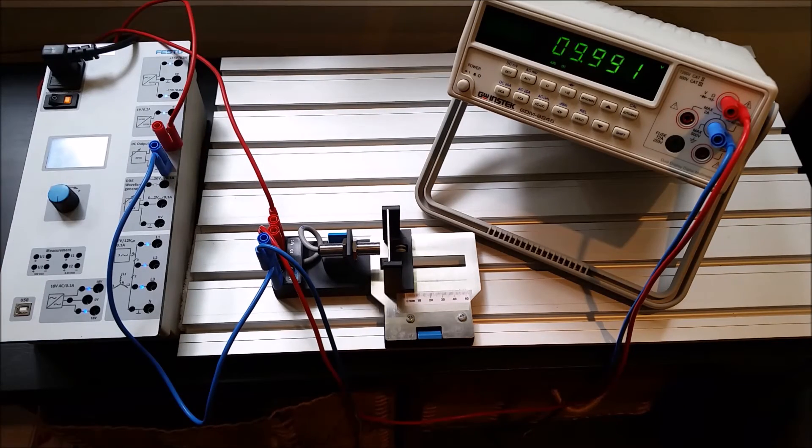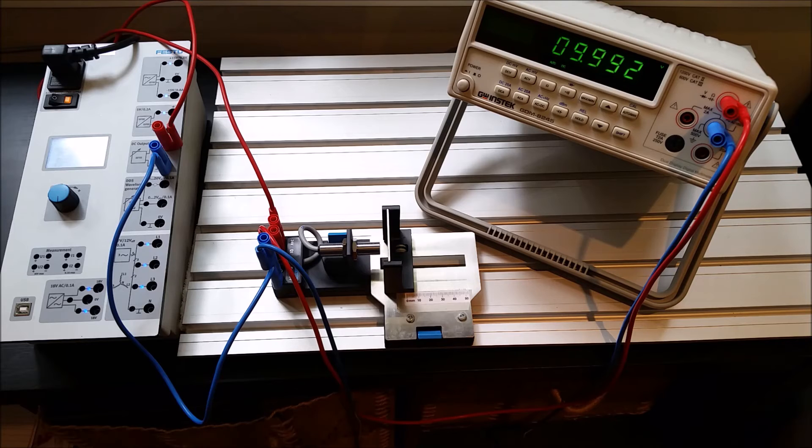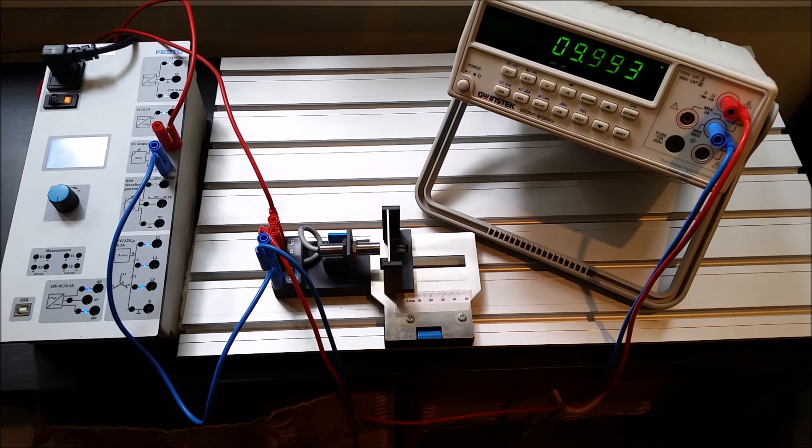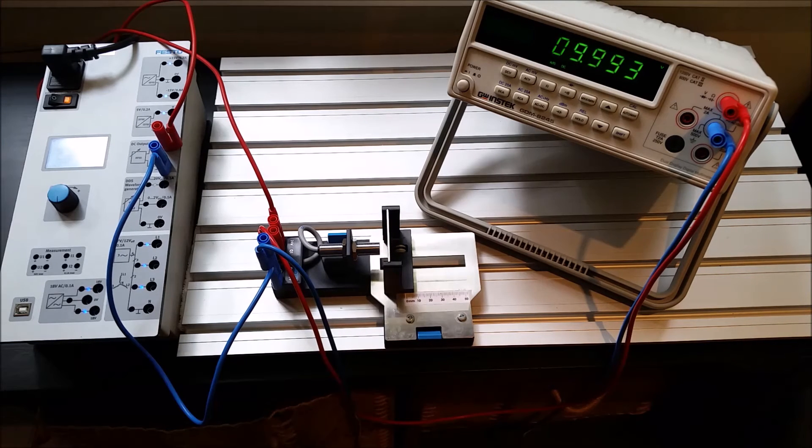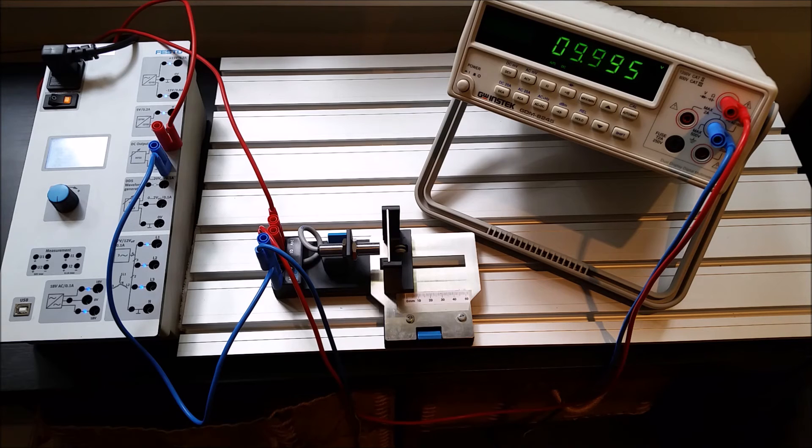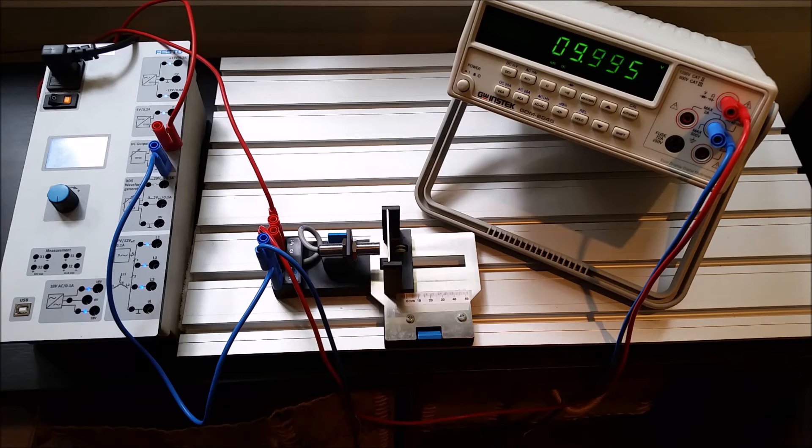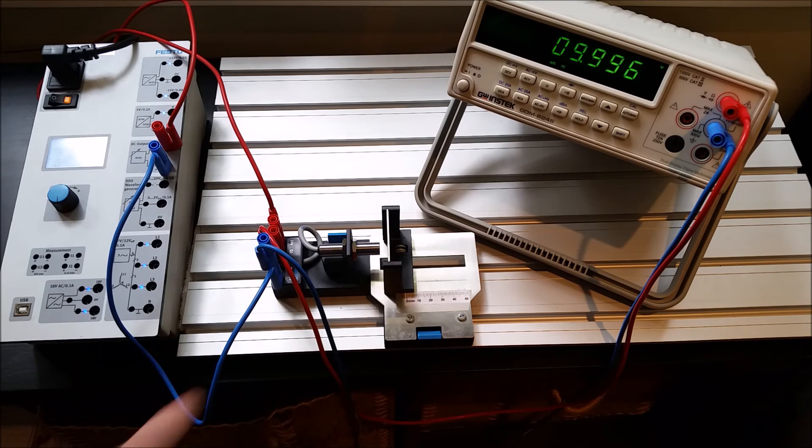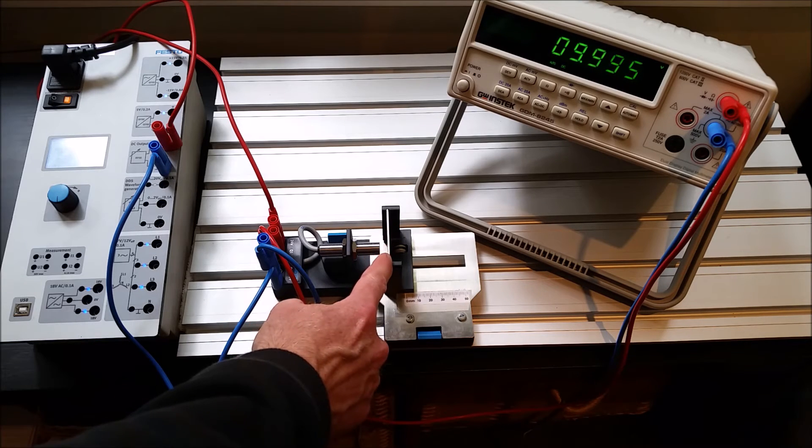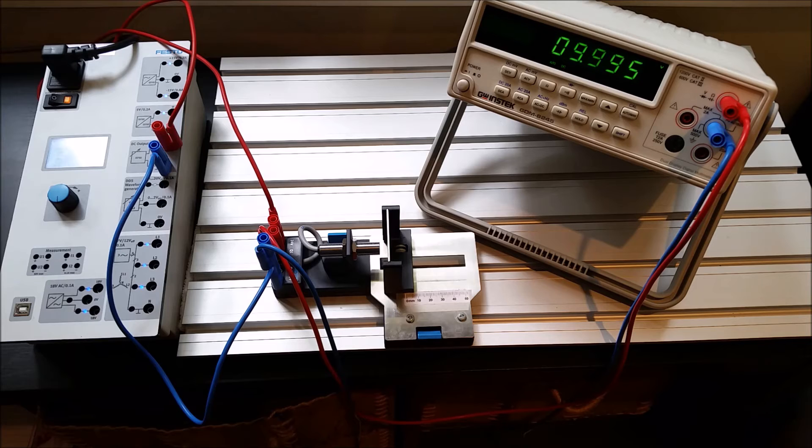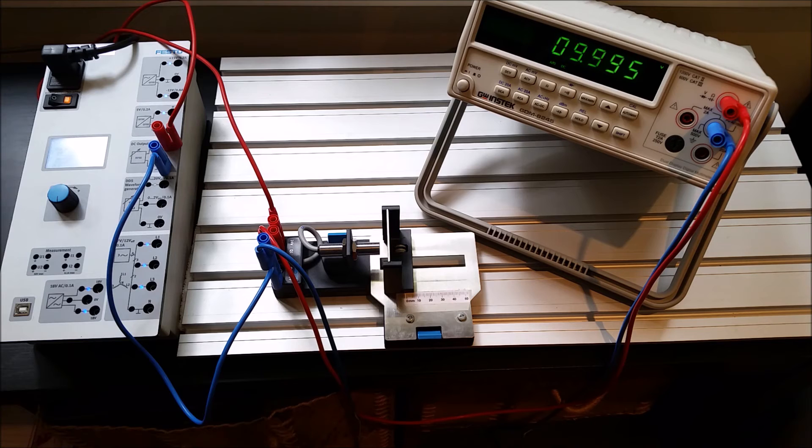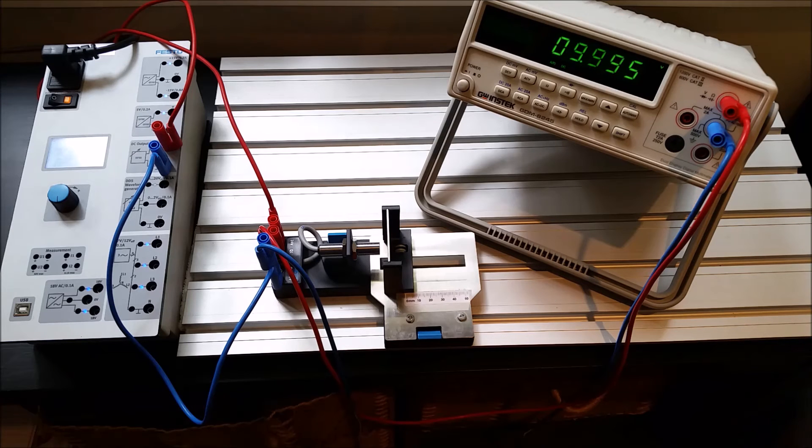So it's a linear output of DC voltage going from 0 all the way up to 10 volts DC. So your PLC could be set up to look at a 0 to 10 volt DC input. It may also be able to see a 4 to 20 milliamp output. So we're going to change some wires around here and look at our current output. But now you can see that based on the distance that the target metal is from the sensor, this is now giving us a linear output signal at the DC voltage that mimics that distance of the target from the inductive sensor.